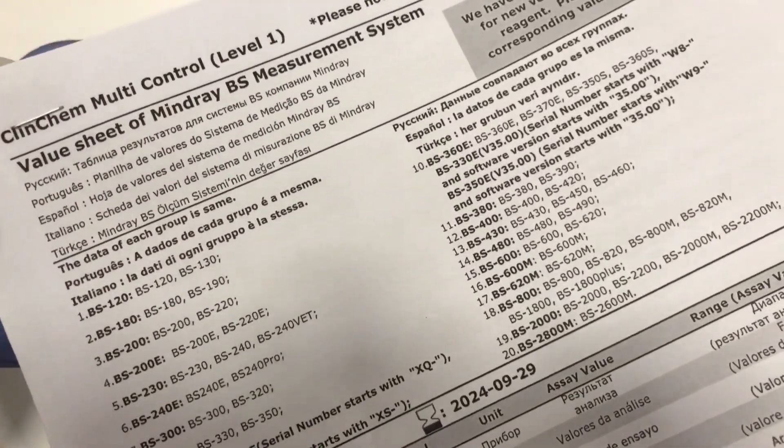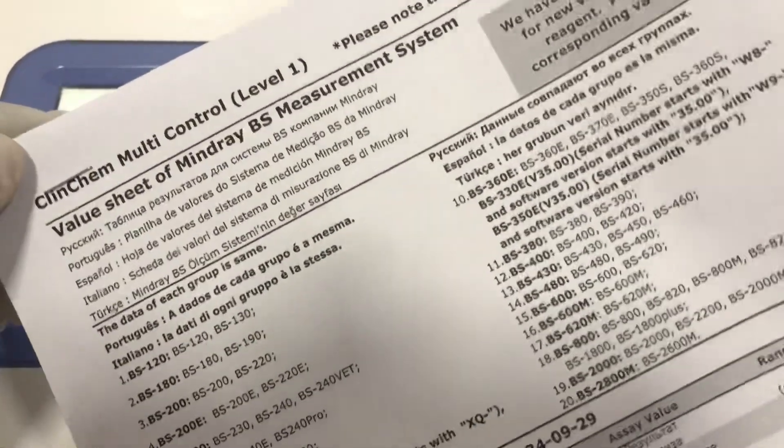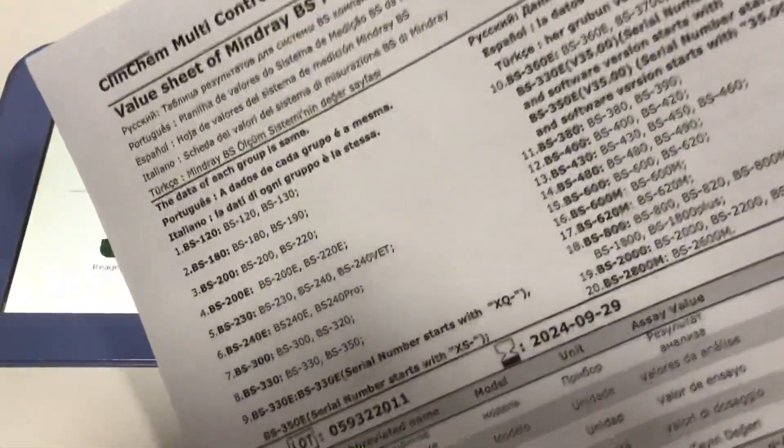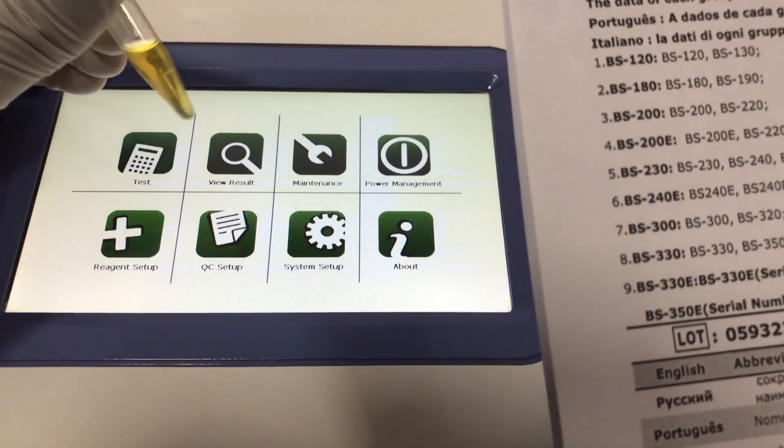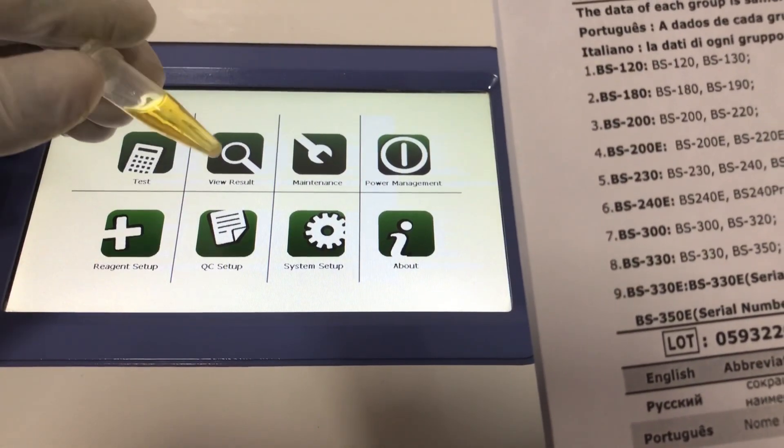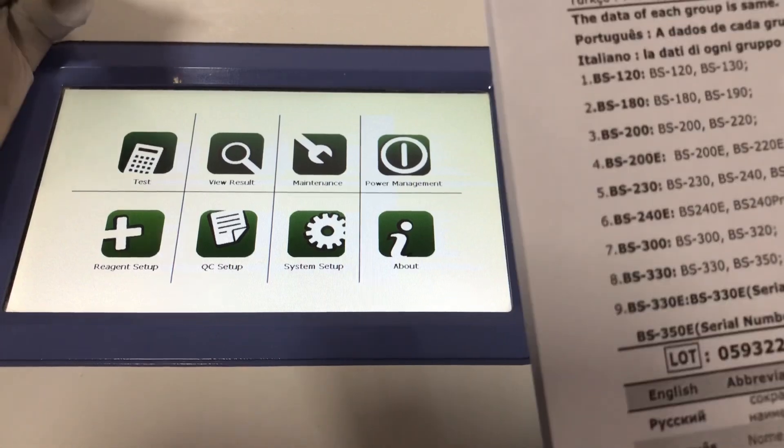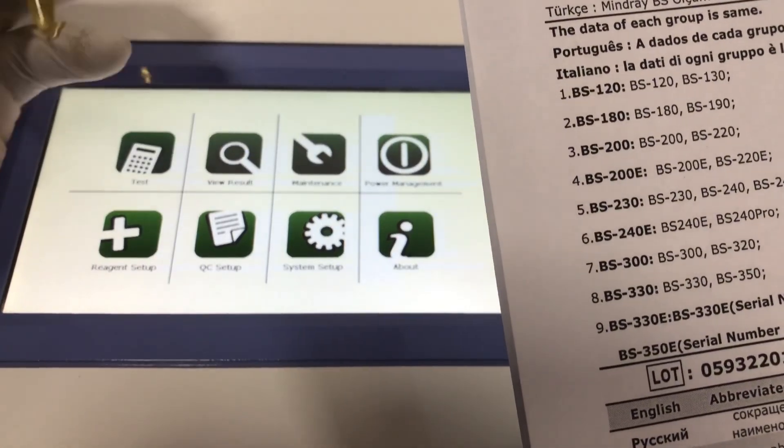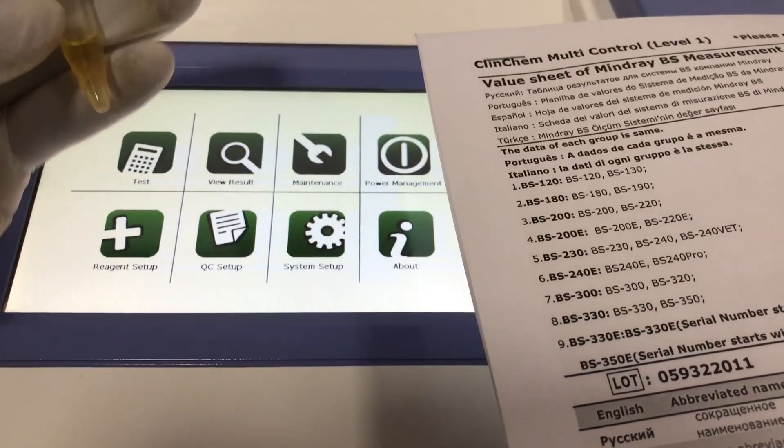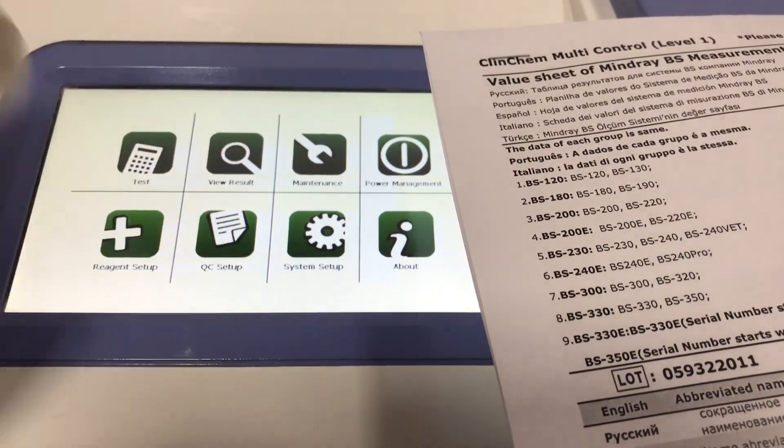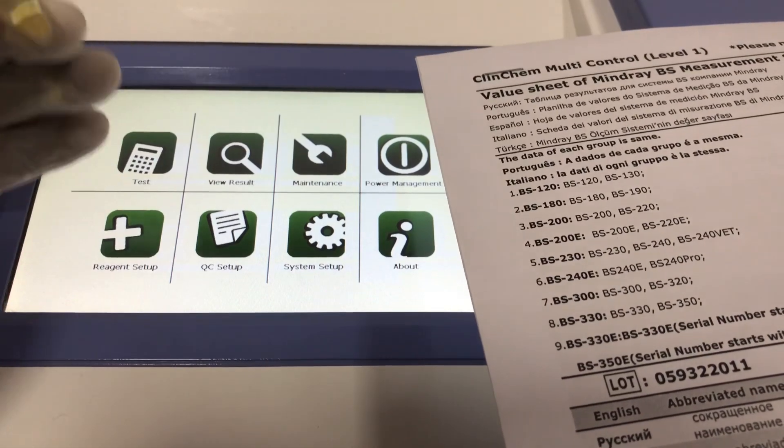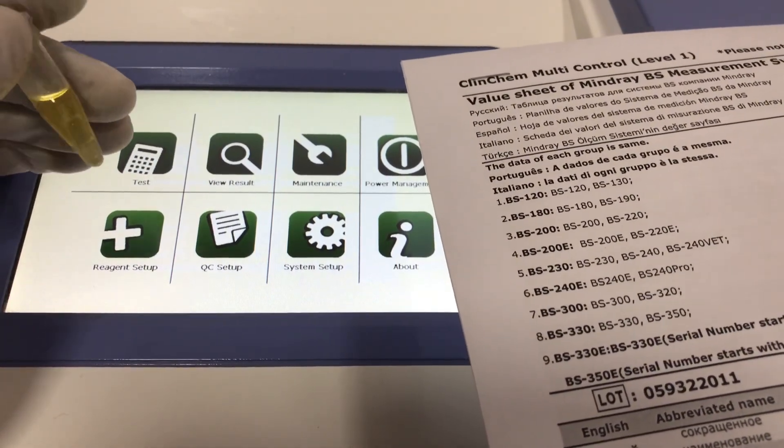The control samples come with their own value sheets for the measurements. The control samples mimic the human sample, so they come with known values. Let's say albumin - they'll give you the expected value for the albumin and then also give you the standard deviation. When you run it on your machine you are supposed to get the same thing. When you get the same thing it simply means that your machine is running effectively.